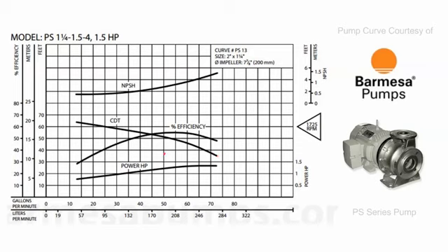What this particular curve shows that the first curve that we looked at did not show is the efficiency curve, which is very interesting, and it also kind of proves a very common rule that is applied pretty broadly in the pump industry. When looking at a pump's performance curve, it's generally accepted that roughly the middle of the pump curve, and we're talking again about the pump's performance curve, is that the middle of the curve in most cases is your best efficiency point.